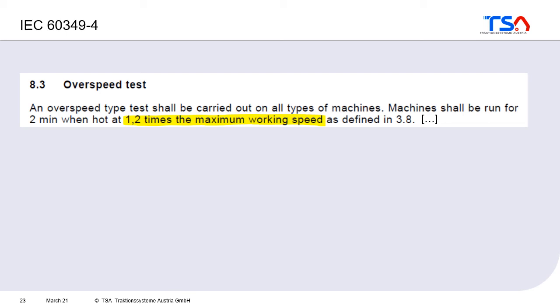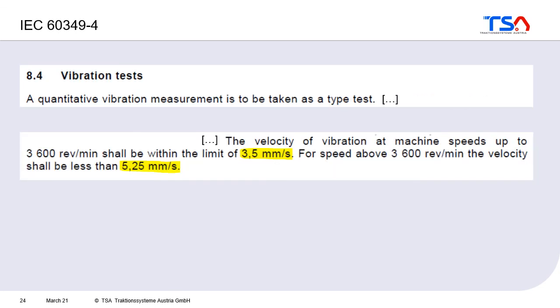To verify mechanical integrity, an overspeed test is conducted at 1.2 times the maximum working speed, after which the machine is typically disassembled and inspected. The standard also provides limits for the maximum vibration velocity.